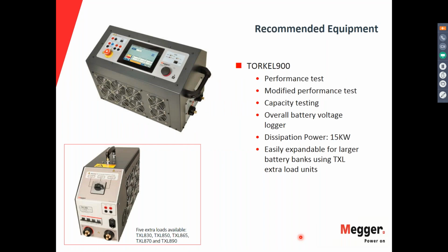The last portion of the presentation is to show the recommended equipment that we have for this test. As a load bank, we have the Torkel 900, an instrument that you can use to run any of the tests that we mentioned today. You can do a performance test or a modified performance test. It will give you the capacity value. It will even log the battery charging process. Once you have completed the test, it can be left connected to monitor how the battery charges.